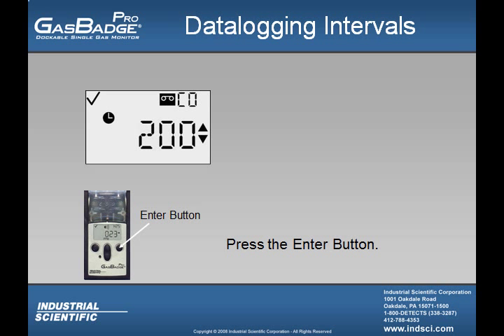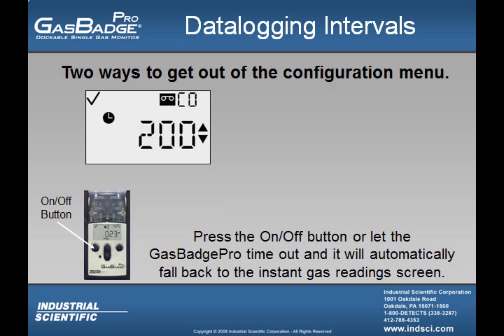Once the user has the Gas Badge Pro's data logging interval set up, they must press the enter button and that value is now stored in the instrument. There are two ways of getting out of the configuration mode: the user can press the on-off button, or they can let the instrument time out, after which the instrument will go directly back to the instant gas reading screen.